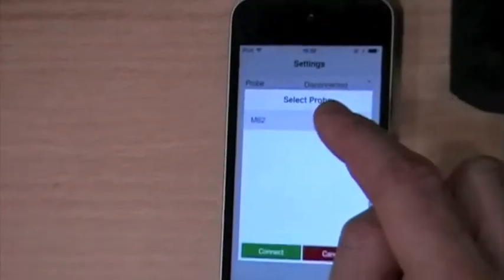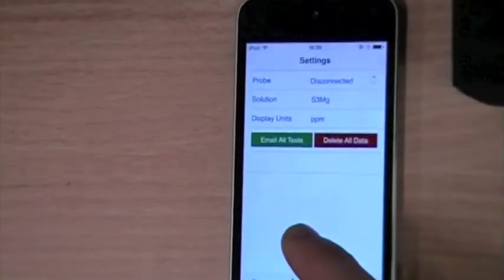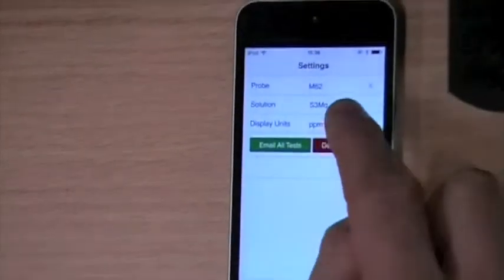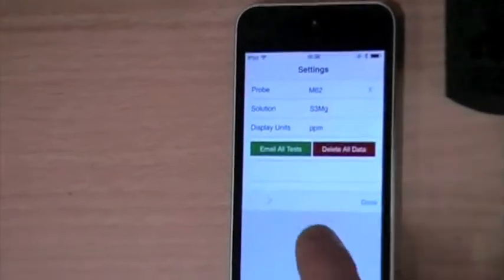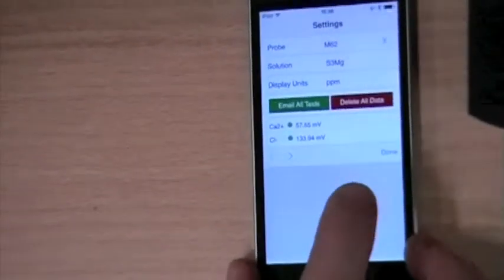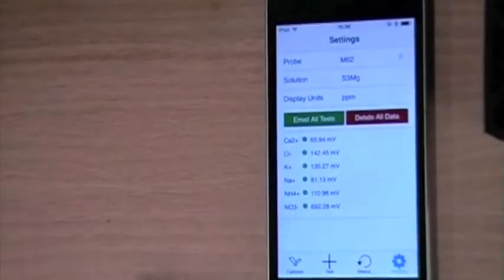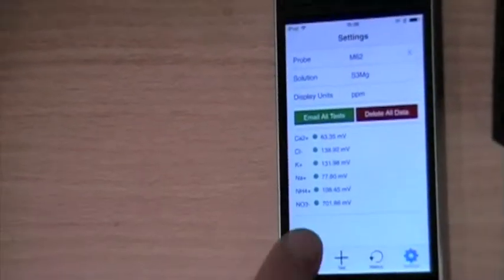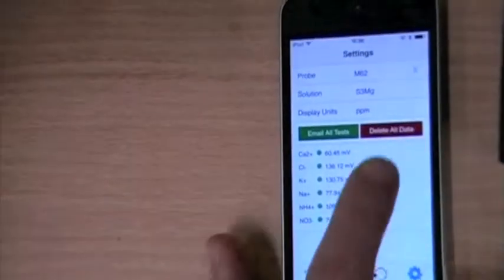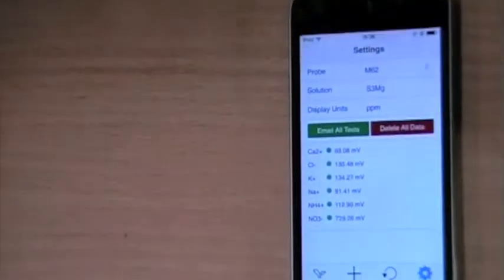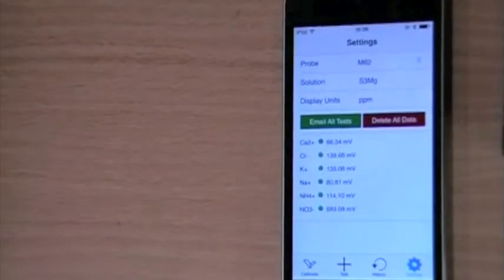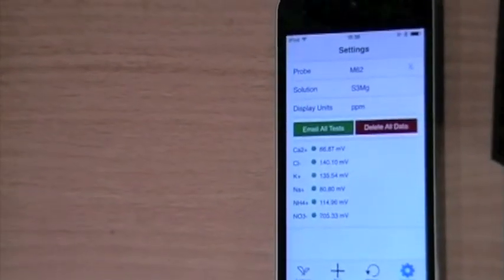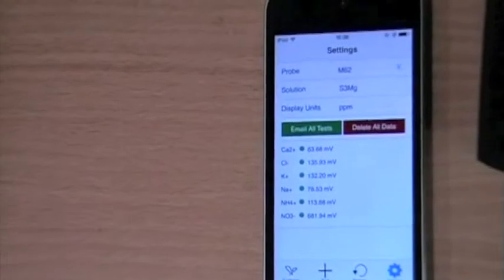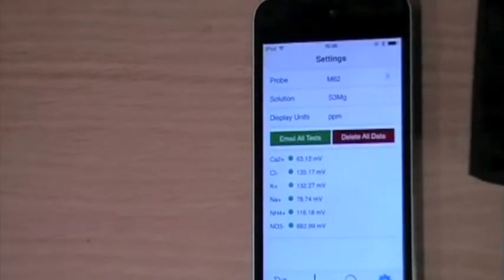Select the probe. Select the solutions. Most commonly S3Mg. Okay. It's a bit stable. You should see some millivolts. So that's the ions picking up, the sensors picking up the charge of the ions. Okay, so now go to calibrate.